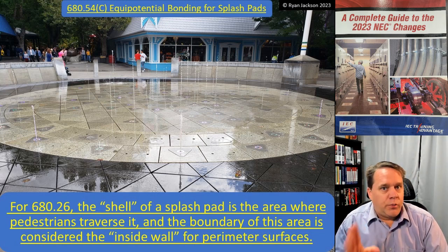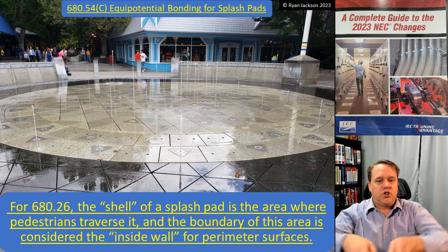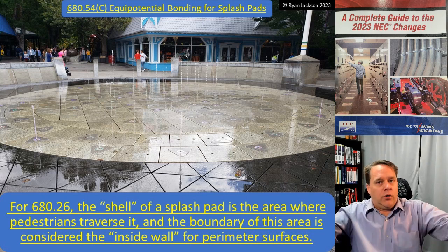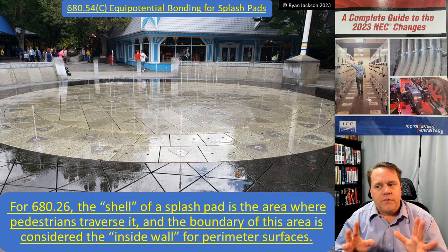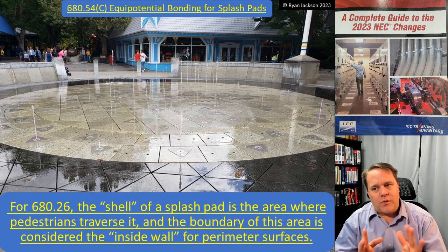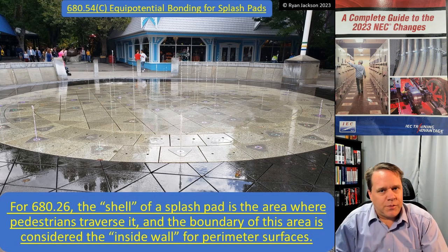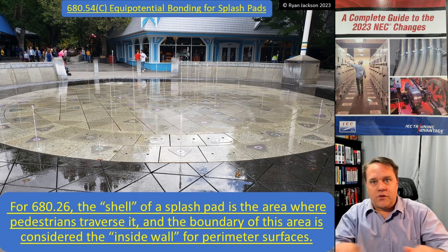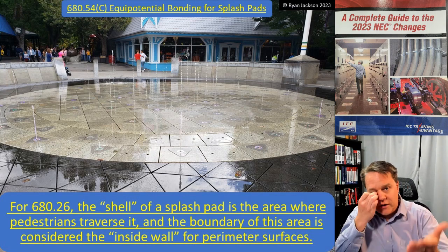We already talked about perimeter surfaces in 680.26 for swimming pools — you bond the pool shell itself and then go out three feet and bond the perimeter surface. But if you don't have a pool and all you have is a flat surface like a splash pad, what's the shell and what's the perimeter? Where does it start and where does it end?